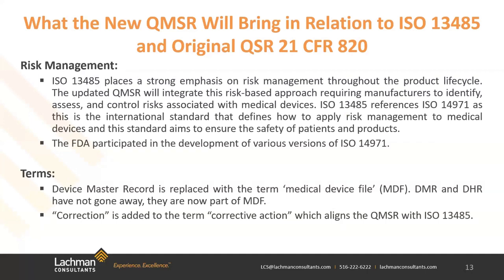Continuing on from there, we've talked about risk management. Risk management is a big component of ISO 13485. Now, the FDA states that it does not include ISO 14971, but emphasizes elsewhere in the preamble that it incorporates risk management as outlined in 13485, which of course references 14971. You have to remember that the FDA recognizes 14971 as a consensus standard. So it's not a mandate, but it considers compliance to 14971 as fulfilling the regulatory requirements for risk management.